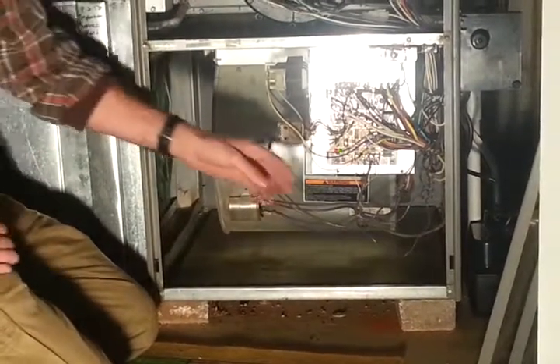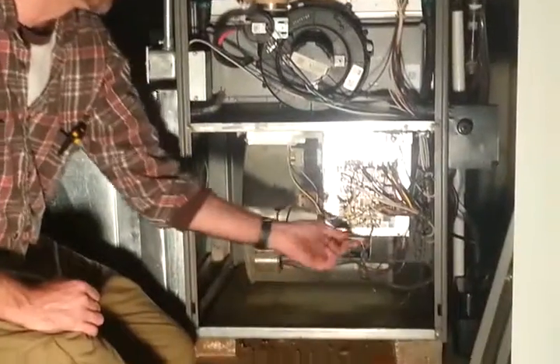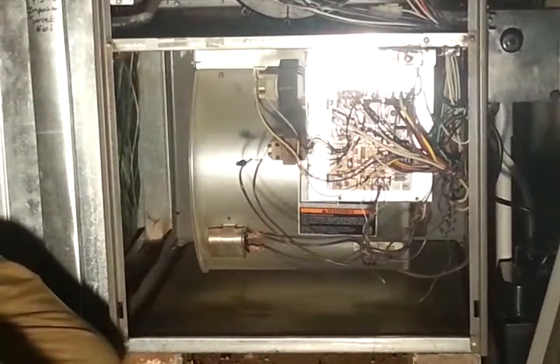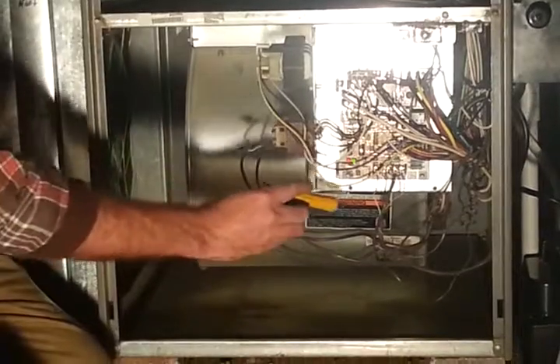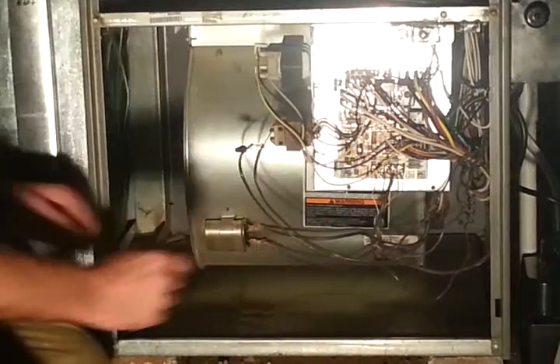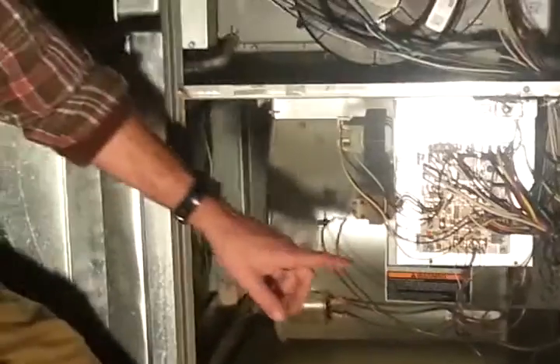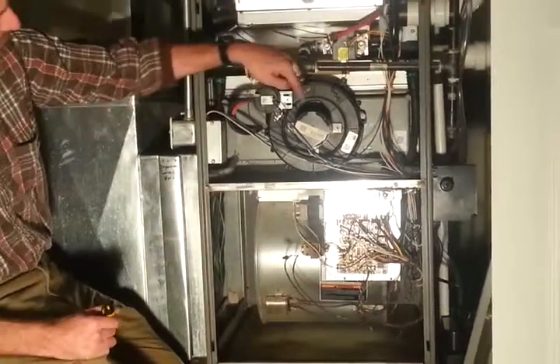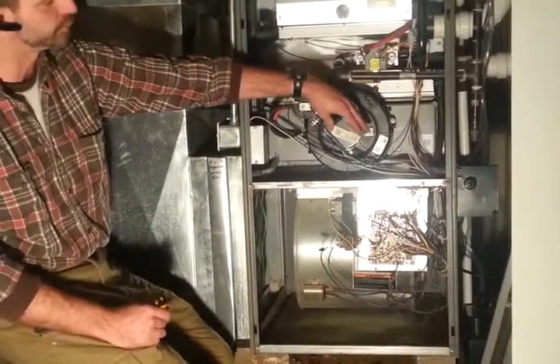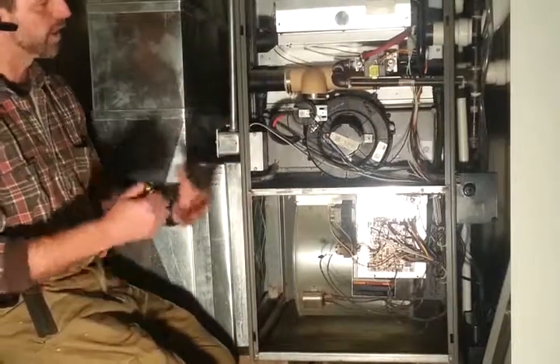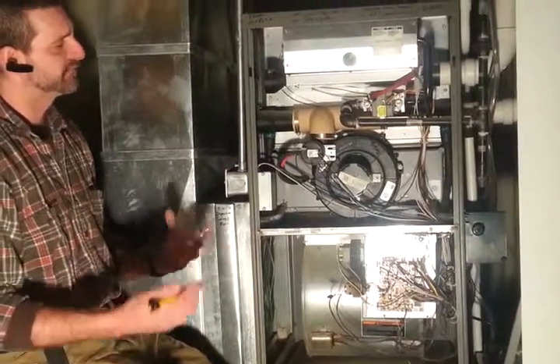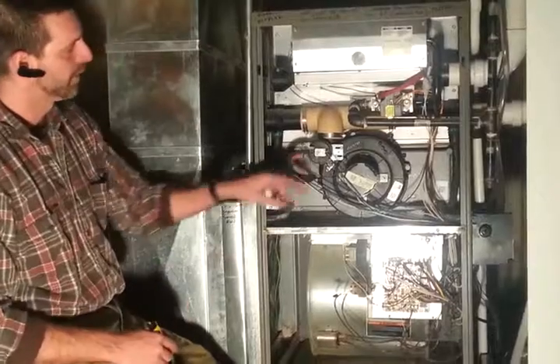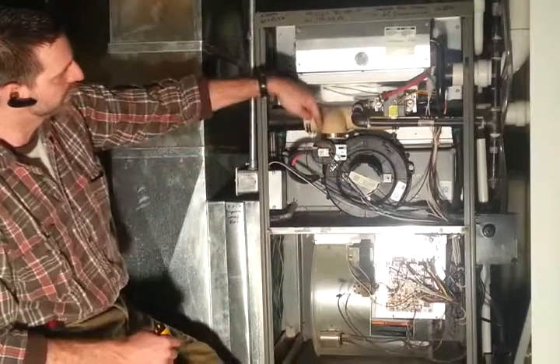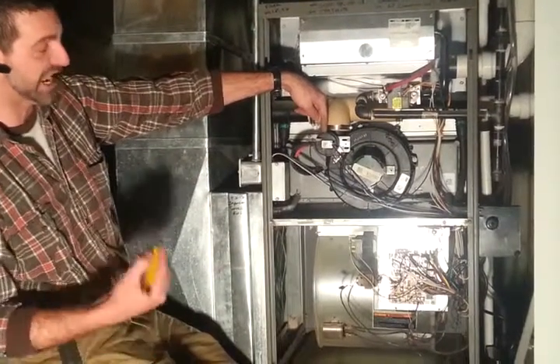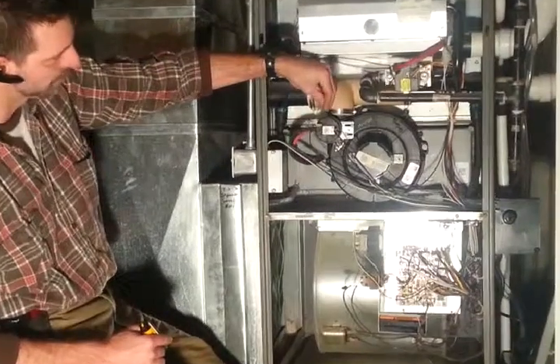Then we have several wires that come back from your thermostat. When we're talking about heating, we're talking about the white wire. Right now we can see that we've got power on that white wire. We've got 24 volts coming back down on the white wire, which has initiated the starting process. You see, the very first thing that happens is my induced draft motor will run. This will run, it'll vary, somewhere between 15 seconds and a minute and a half. What happens once he runs and the associated vacuum switch is satisfied, it'll close up.